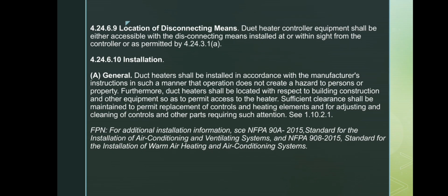Next slide. The disconnecting means for a duct heater must be installed at or within sight of the controller unless otherwise allowed by the code. For installation, duct heaters must follow the manufacturer's instructions and must not create hazards. They must also be placed so that controls and heating elements can be accessed, replaced, and cleaned when needed. Adequate clearance must be maintained, and additional guidance is available in NFPA 90A and NFPA 90B.